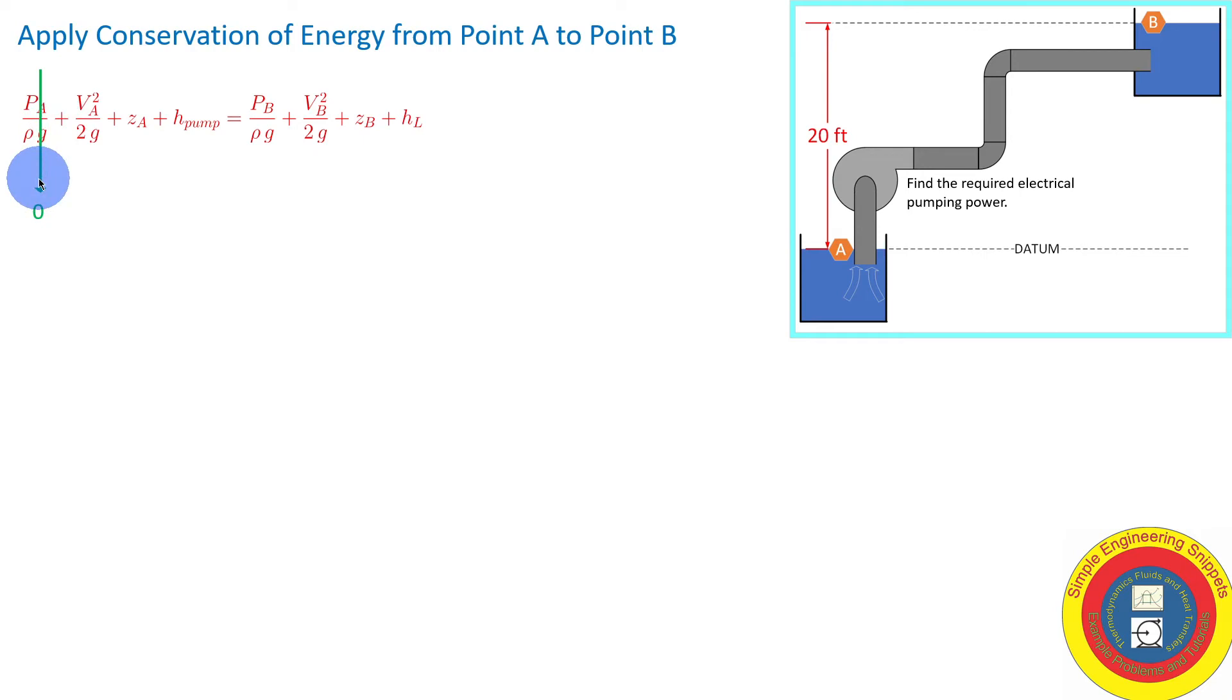We're at atmospheric pressure, so pressure at alpha is 0. It's a large tank, so velocity at alpha is 0. We defined our elevation to be 0. The pressure at bravo is also atmospheric or 0. It's a tank at bravo, so velocity is also 0. We can simplify and solve this equation for the head of the pump, which is equal to the difference in elevation plus the head loss. So we need to calculate the head loss.